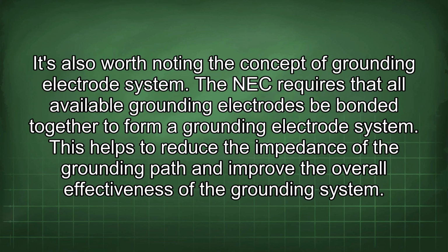It's also worth noting the concept of grounding electrode system. The NEC requires that all available grounding electrodes be bonded together to form a grounding electrode system. This helps to reduce the impedance of the grounding path and improve the overall effectiveness of the grounding system.